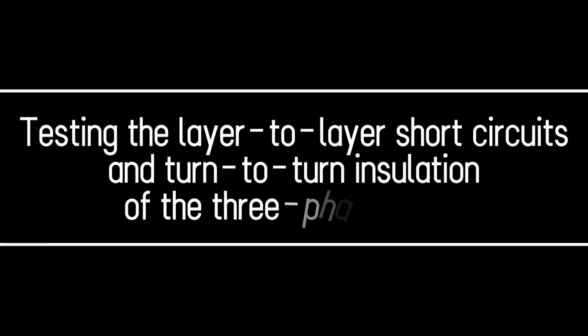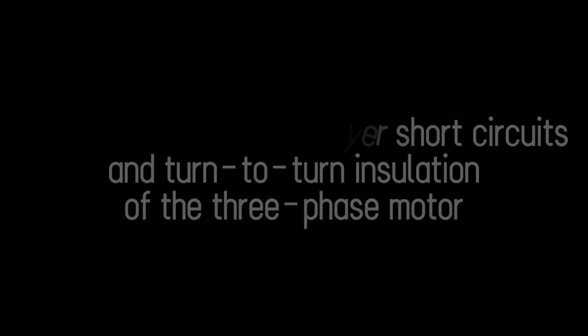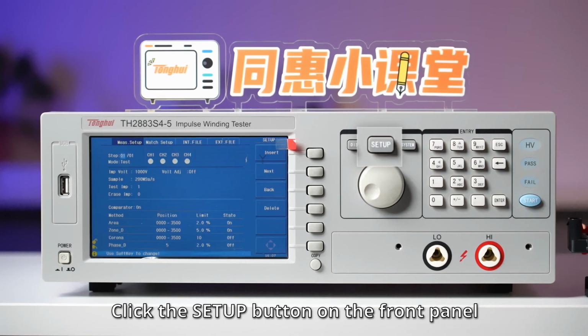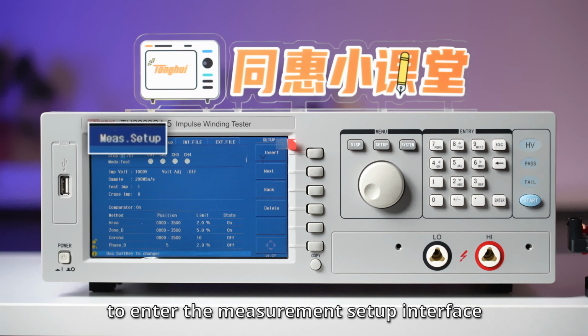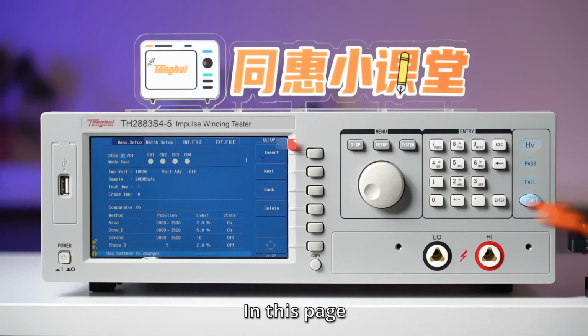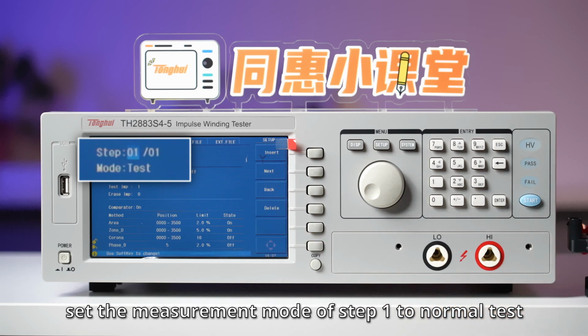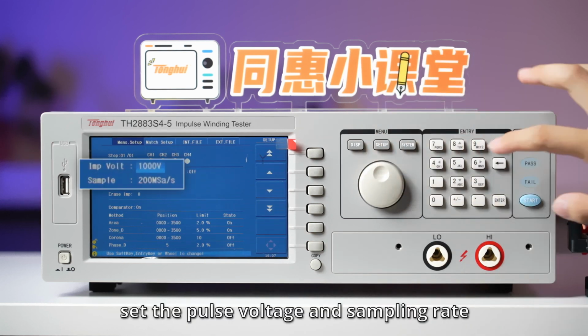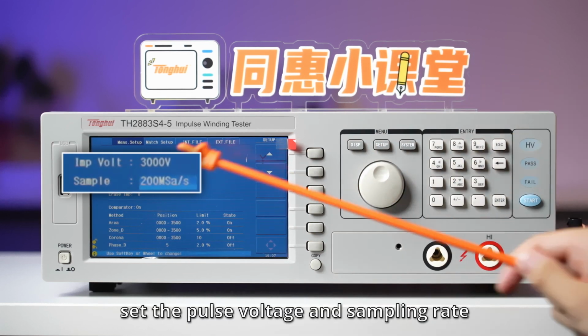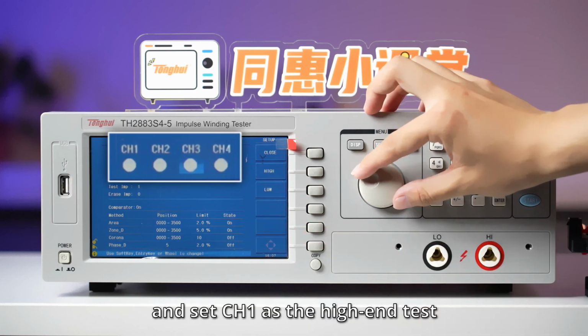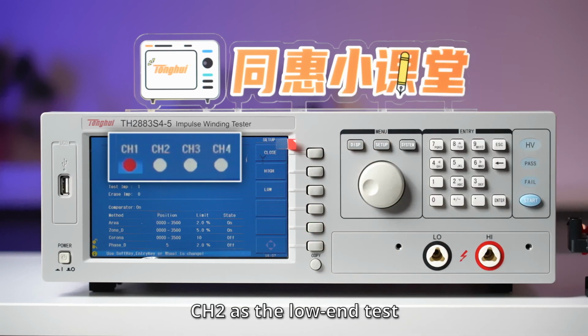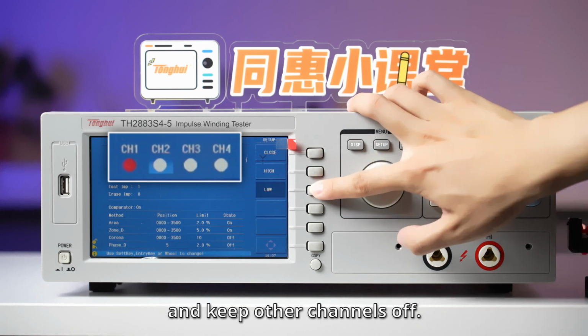Testing the layer-to-layer short circuit and turn-to-turn insulation of 3-phase motor. Click the Setup button on the front panel to enter the measurement setup interface for channel testing. In this page, set the measurement mode of Step 1 to normal test. Set the pulse voltage and sampling rate, and set the Channel 1 as the high-end test, Channel 2 as the low-end test, and keep other channels off.